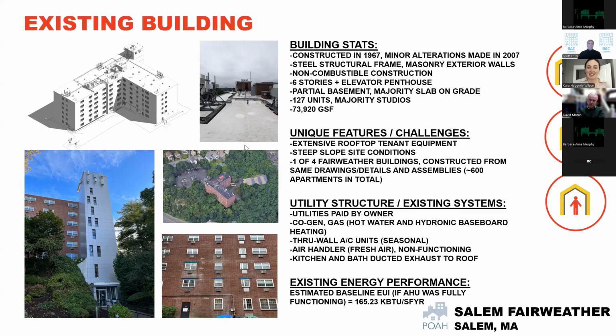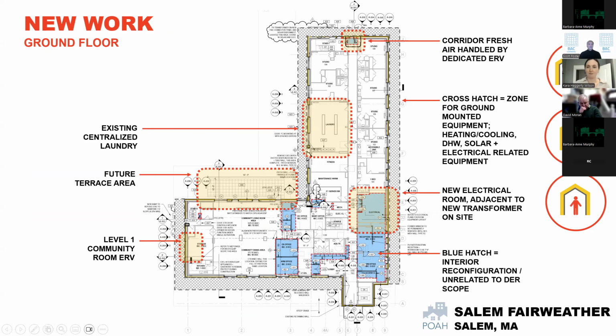So when we look at the existing energy performance and try to figure out the estimated baseline EUI to qualify this building, we looked at it as though the AHU was running, since it should be for code purposes. With that, we came up with a number of 165 kBTU per square foot per year. So a really, really poor performing building, and it seemed really ripe for some intervention.